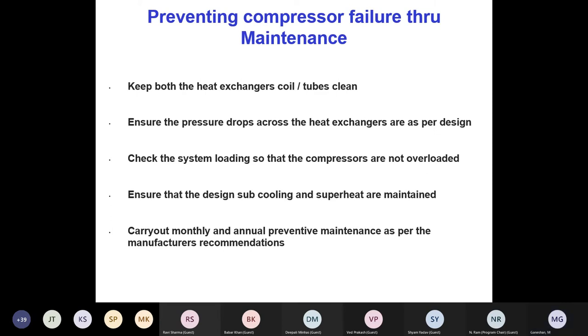Then you again have to do descaling, especially if there is more salt, especially the one we call silica. When silica has deposited inside, you can see very polished silica inside the tube, which indicates silica salt is there. That is a very deadly, dangerous salt. You cannot remove it. To remove it, even with acid, you have to heat it and pour it in to get it out. So all this we can avoid.